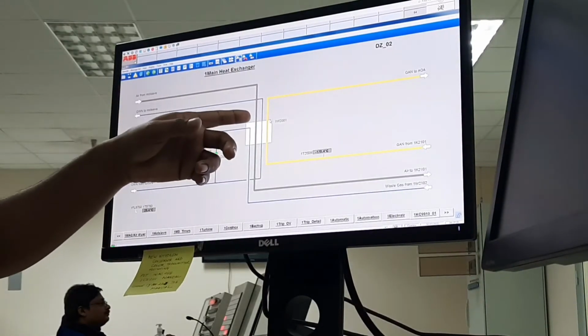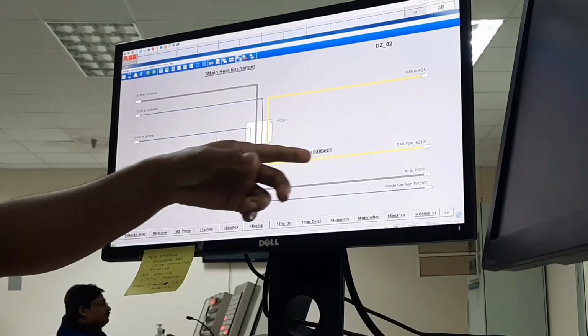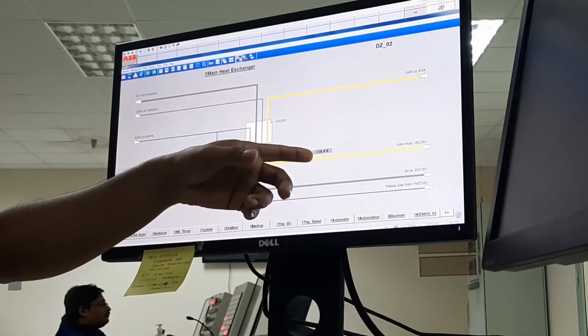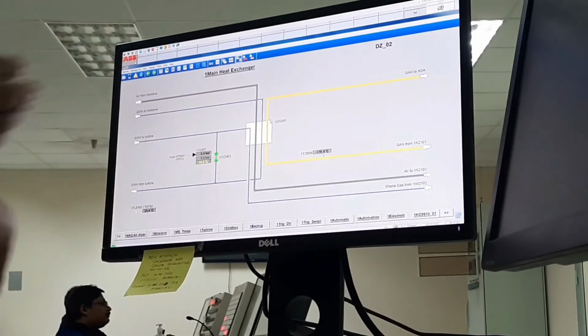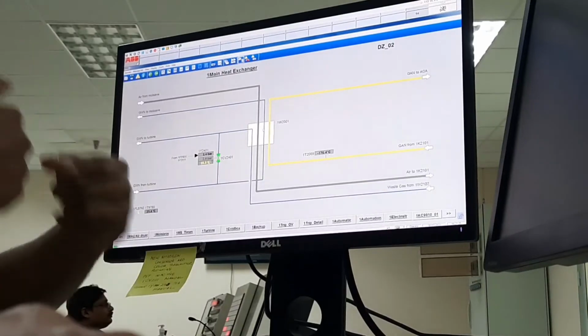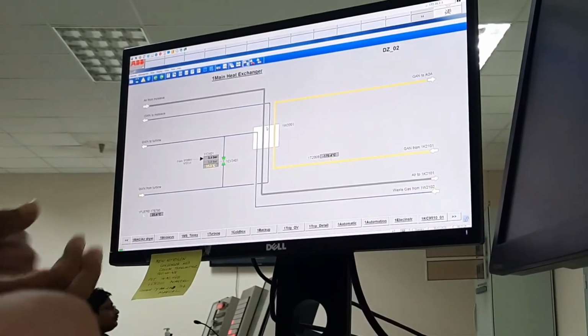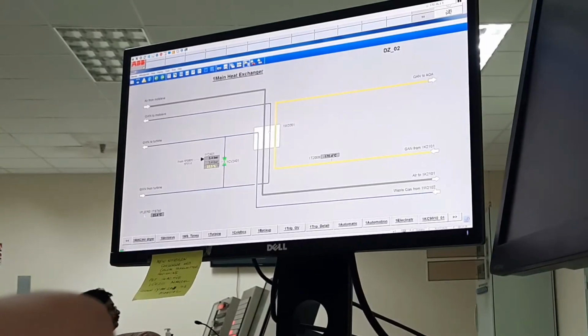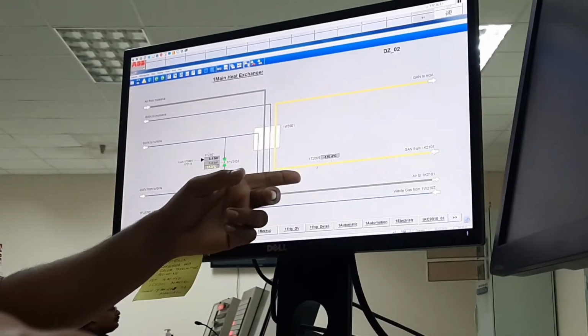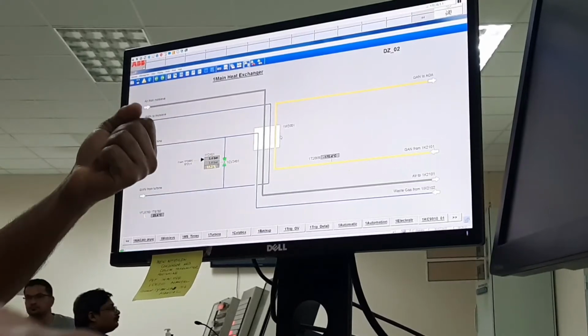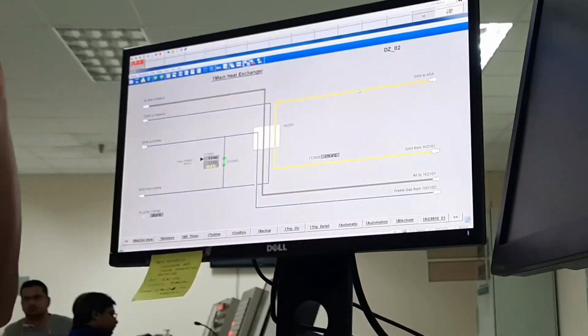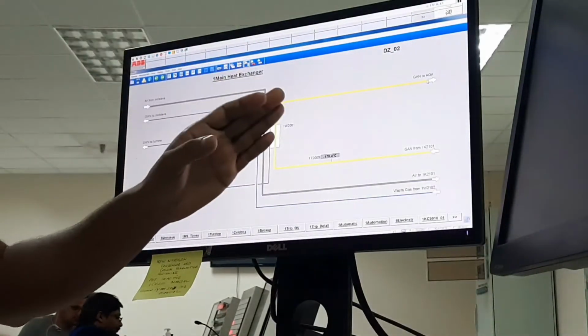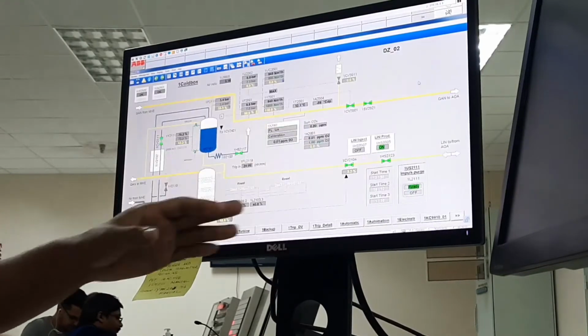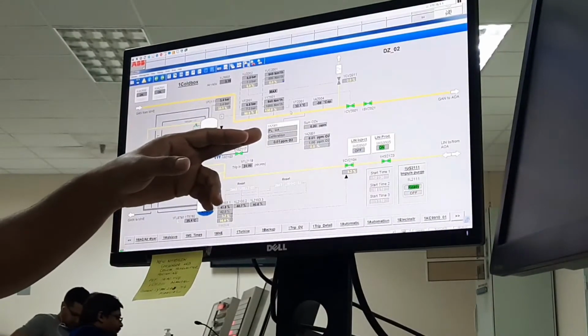When it passes through the main heat exchanger, it will gain temperature, because the other temperature is 30 degrees and this one is minus 170. They will exchange: one loses and one gains. Yes, like that. So the gaseous product will gain temperature. The temperature increases by around 30 degrees, and after that it goes to the main gaseous product line.